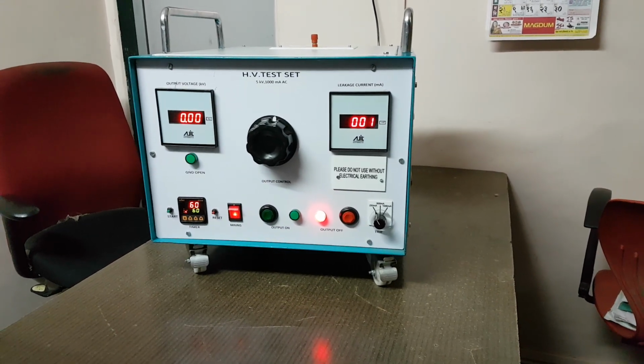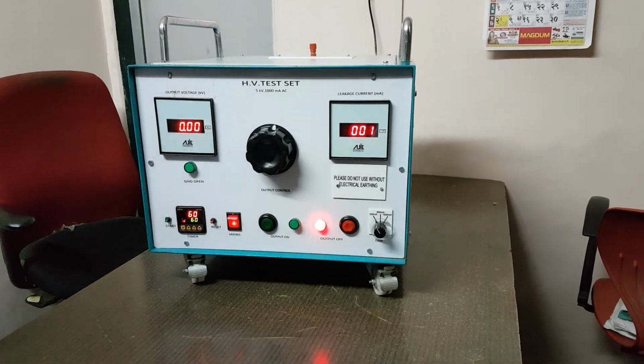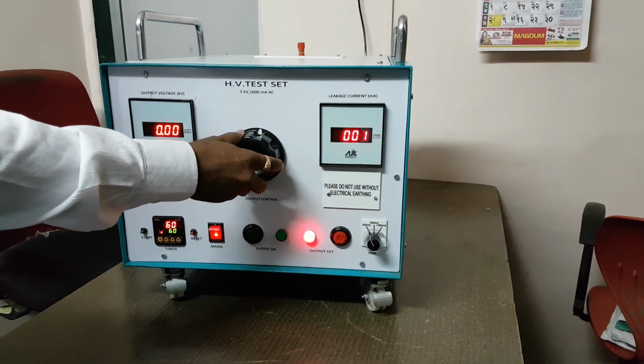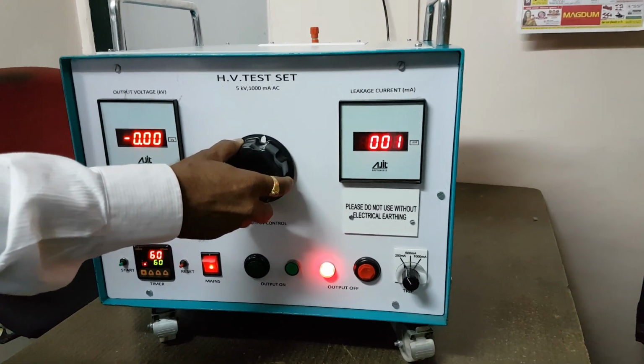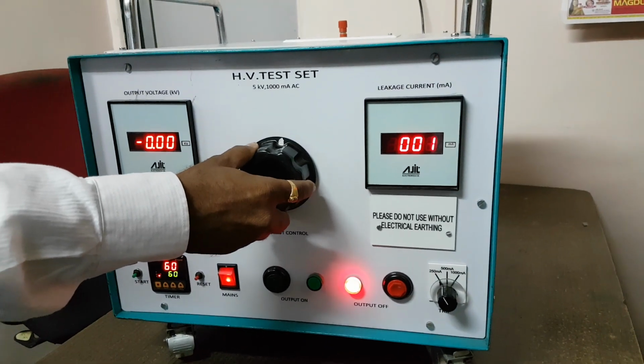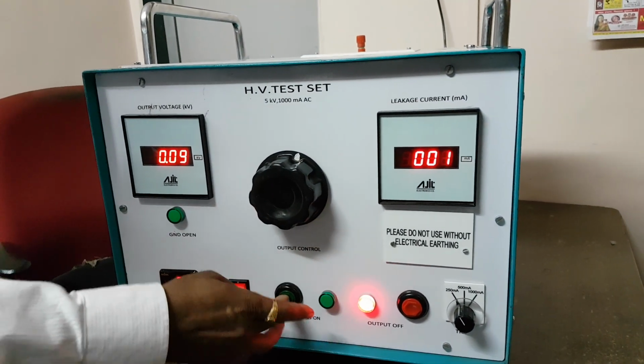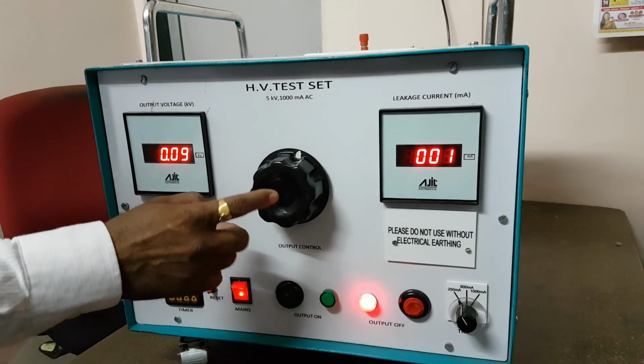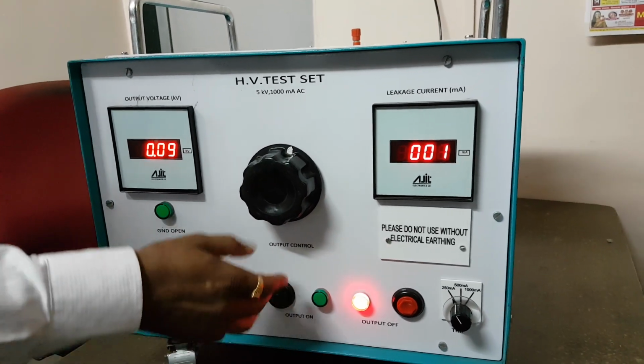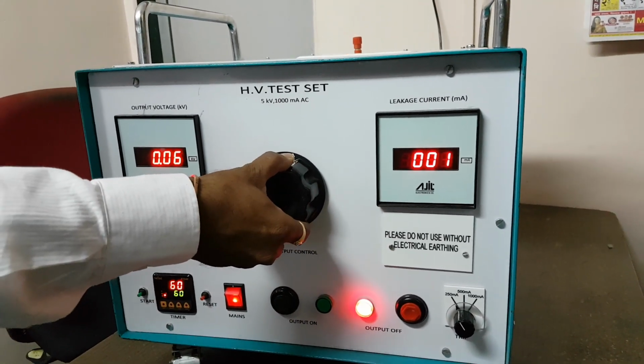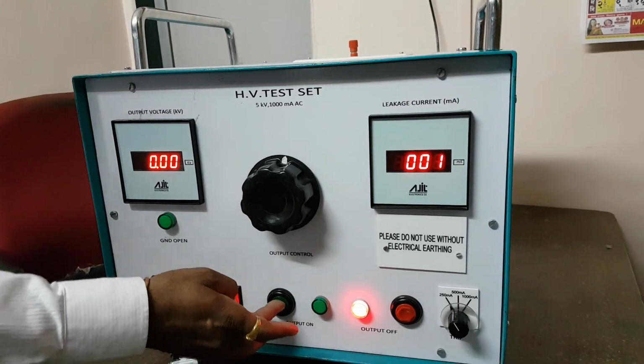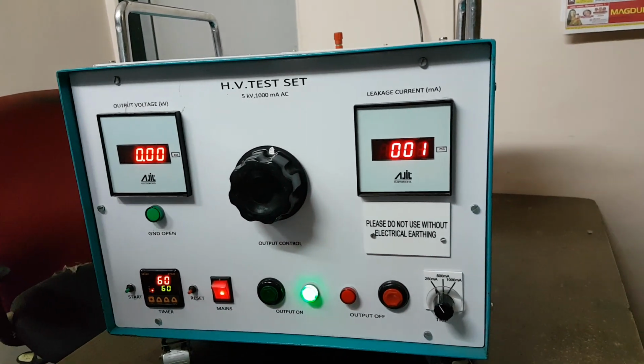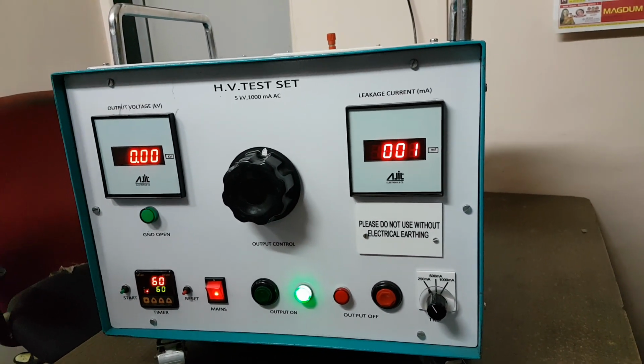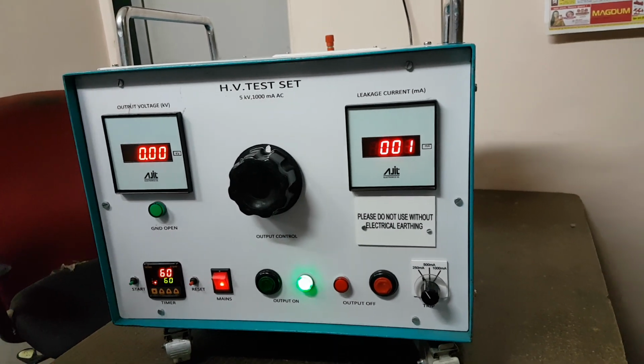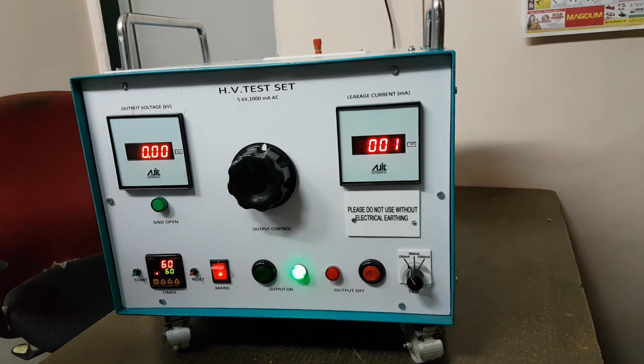Now one more interlock is provided in the instrument, like zero start interlock. This means unless this dimmer stat is at 0, we cannot initiate the high voltage. Now the dimmer is not at 0, so we have to bring the dimmer to 0, and then only the high voltage can be initiated. This is also a safety interlock for the instrument as well as the operator.